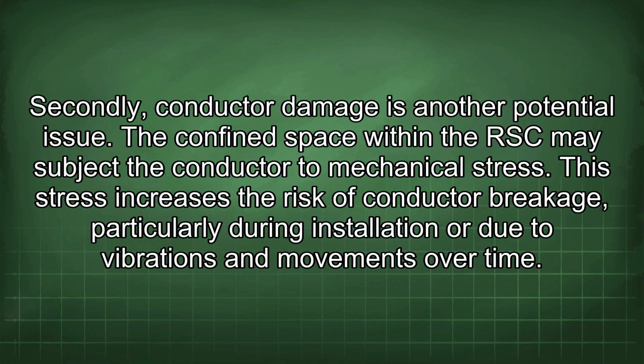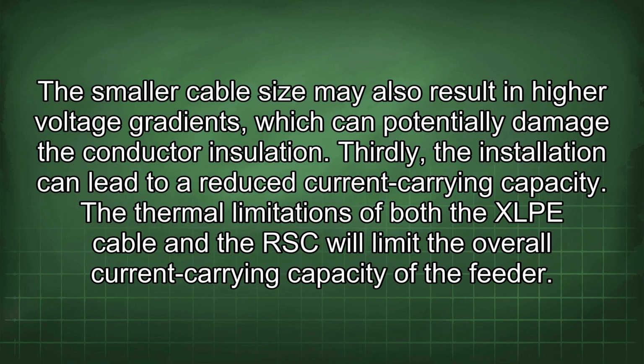Secondly, conductor damage is another potential issue. The confined space within the RSC may subject the conductor to mechanical stress. This stress increases the risk of conductor breakage, particularly during installation or due to vibrations and movements over time. The smaller cable size may also result in higher voltage gradients, which can potentially damage the conductor insulation.